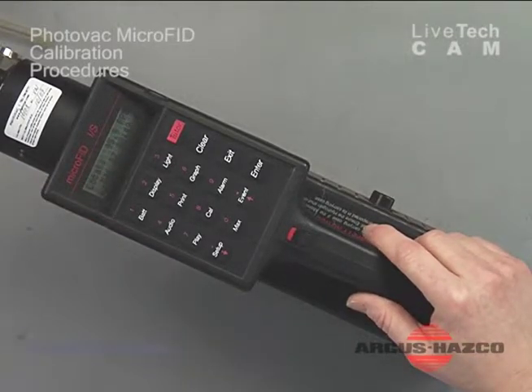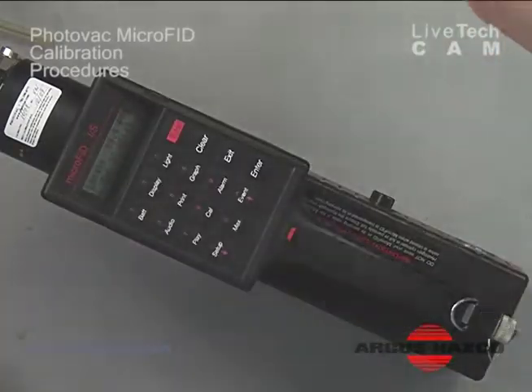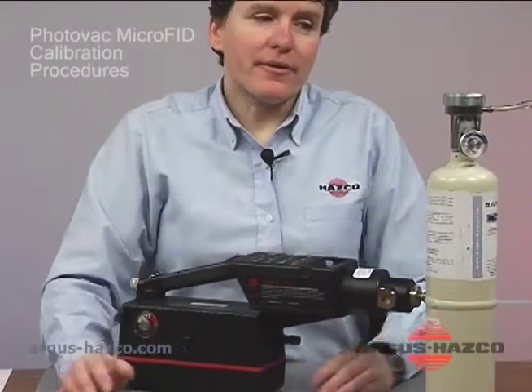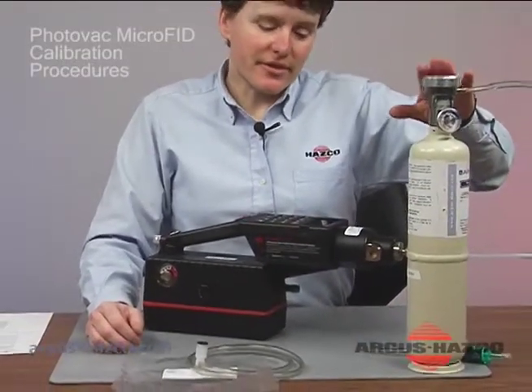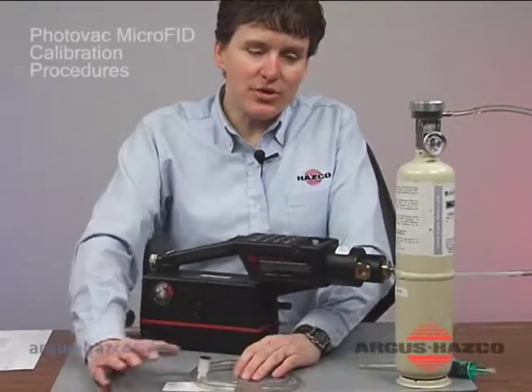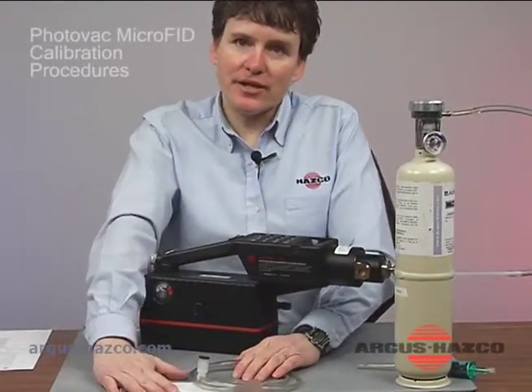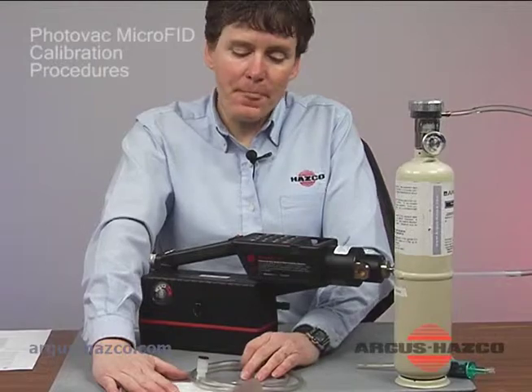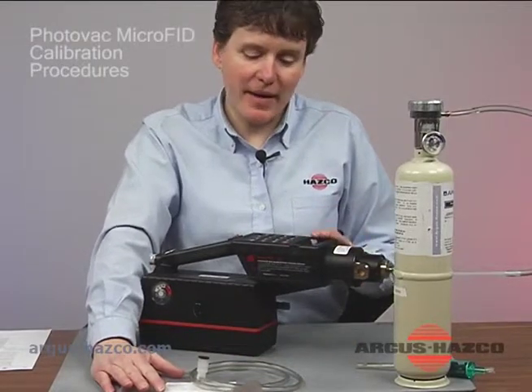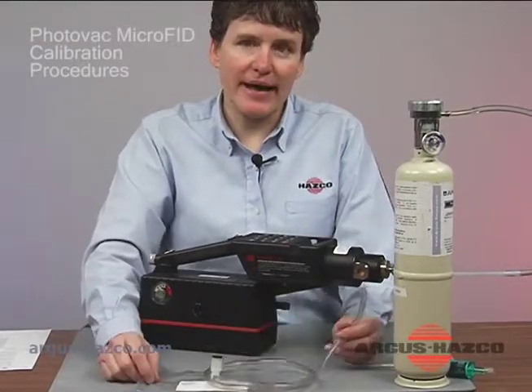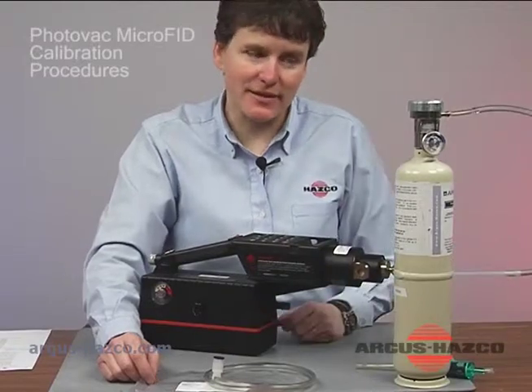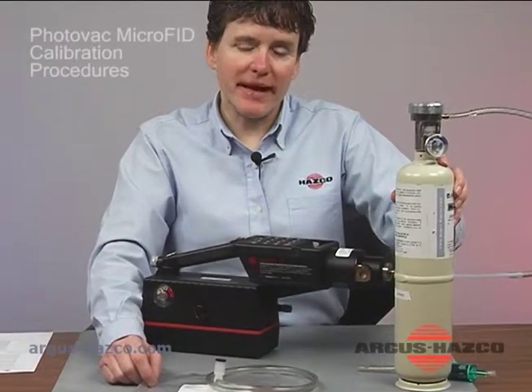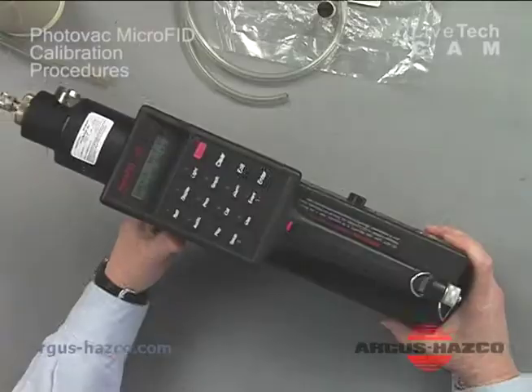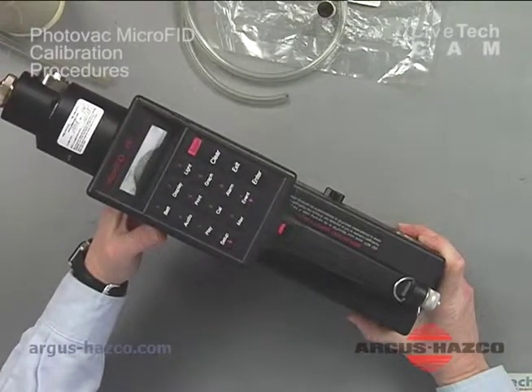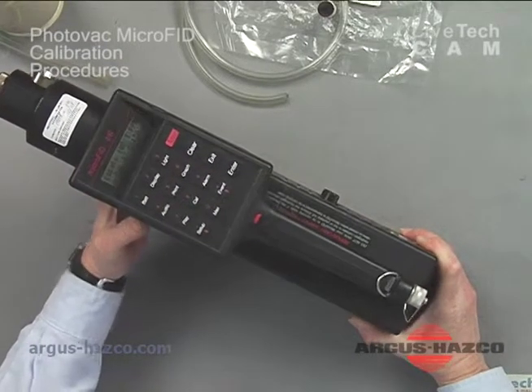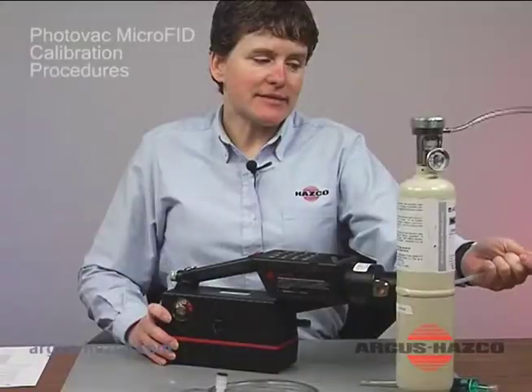Also, you can calibrate the unit with a Tedlar bag if you would prefer, instead of using your cylinder of gas. What you would do is fill your Tedlar bag with your 100 ppm, and when it came to attach your span gas, you would attach your Tedlar bag to the inlet instead of attaching straight from the canister. Our unit is done calibrating and it's reading properly. So what we want to do is go ahead and disconnect my gas.